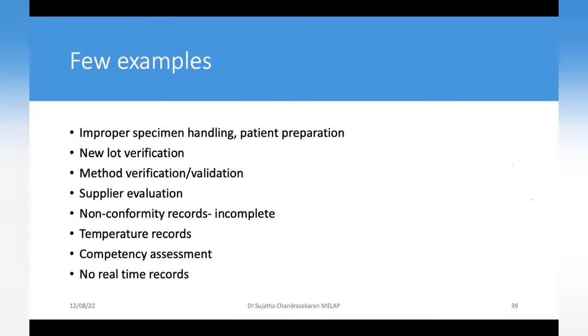Supplier evaluation, non-conformity records, most of the time they are incomplete. If the non-conformity records are not done sincerely, you are missing risks. Temperature records, where you need to write the temperature, not just put a tick. The way we record things, the way we do competence assessments. For example, how often we do a pipetting efficiency in a competency assessment. Somebody in chemistry may be reconstituting the controls or calibrators. If the pipetting is not good, and you have not introduced it in competence assessment, then you are going to have the wrong results throughout. Maybe there are trends, maybe there are imprecisions, it's going to come.